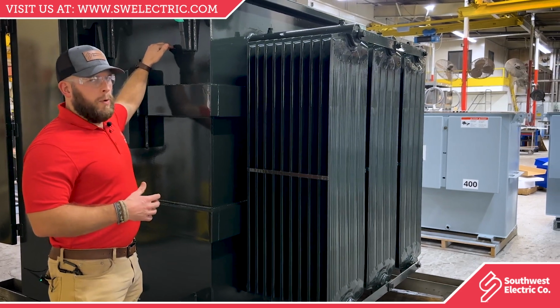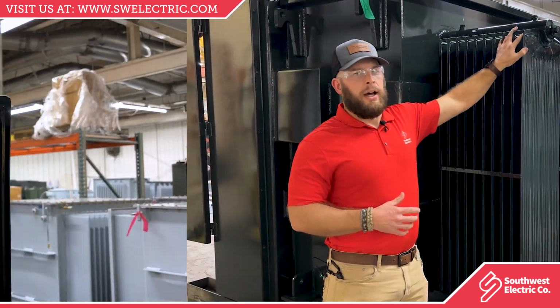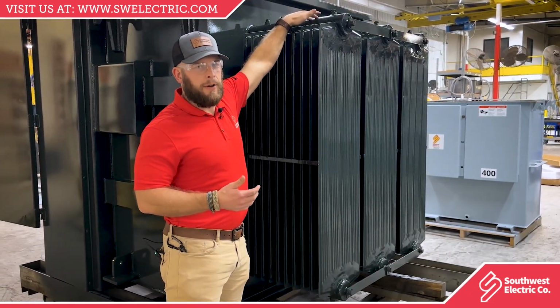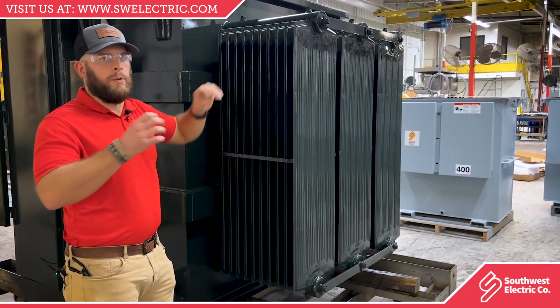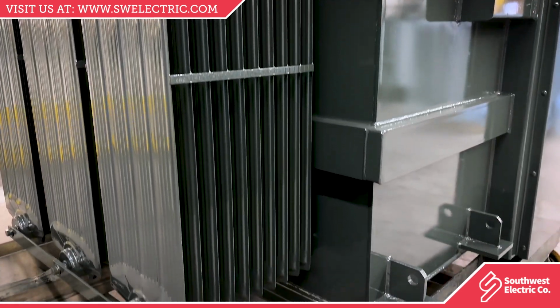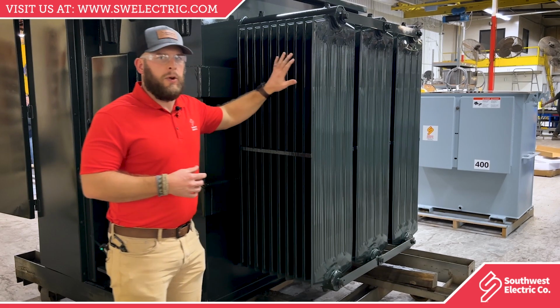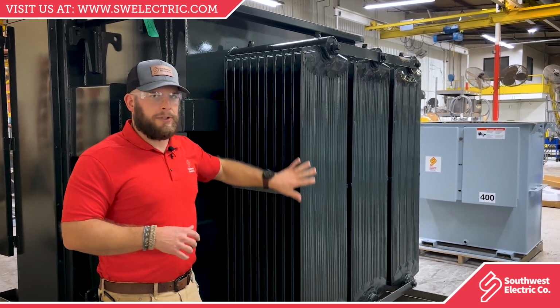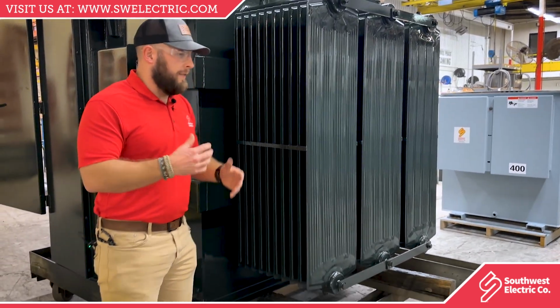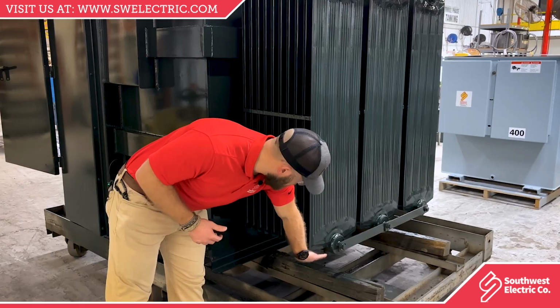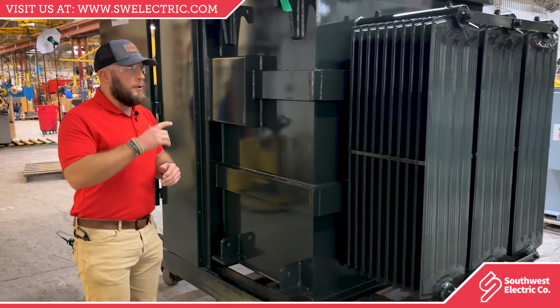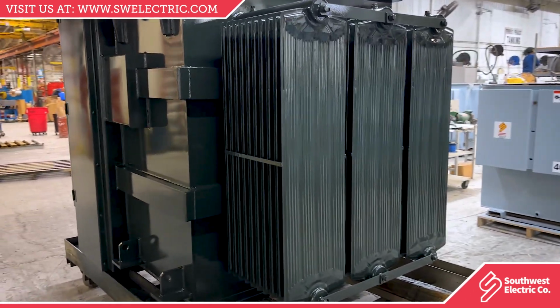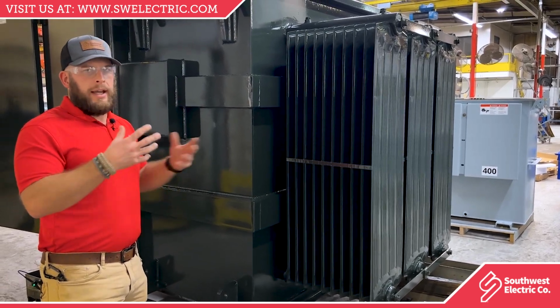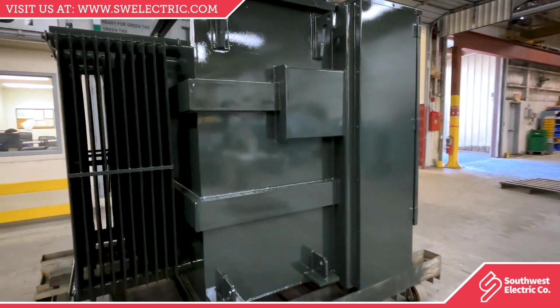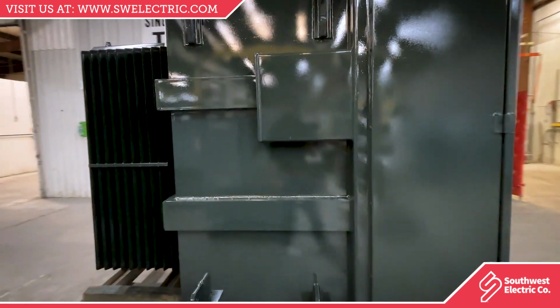So as the transformer oil rises, it will start to flow into these cooling fins, or what we call radiators, through these different headers. And as they come into these cooling fins, it will start to run down each individual fin as it can dissipate heat. So the more surface area you have on these, the more heat you can dissipate. As that heat is dissipated, the oil will cool down and actually start to sink to the bottom of the radiators. And then eventually it will make its way back into the transformer tank by these headers on the bottom side of the cooling fin. So as these transformers are running, oil is constantly circulating. It's natural convection that cools this transformer and keeps it running at a safe temperature for operation. So that's the first reason for using oil in a transformer.